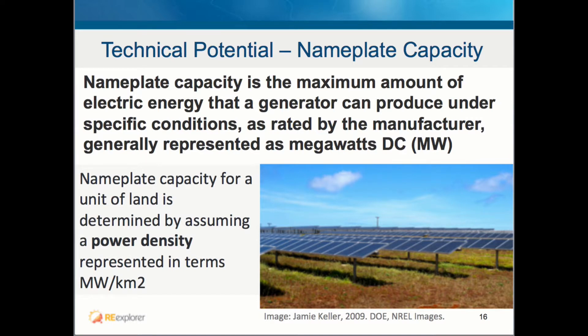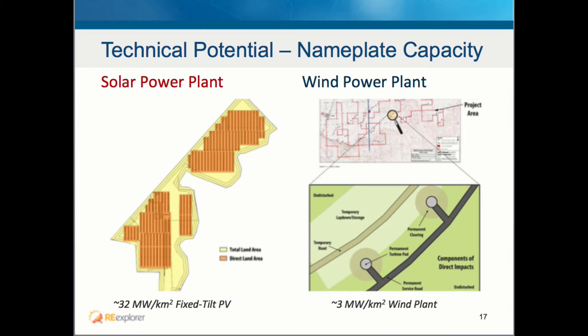With the available land area, we calculate the nameplate capacity. Nameplate capacity is the maximum amount of electric energy that a generator can produce under specific conditions as rated by the manufacturer, generally represented in megawatts direct current. It is calculated by taking the power density times the available land area. For fixed-tilt photovoltaics, we generally use 32 megawatts per square kilometer. Wind, on the other hand, is less dense at around 3 megawatts per square kilometer, because you aren't able to pack turbines closely together for risk of reducing wind potential. These numbers are subject to change as technology advances.